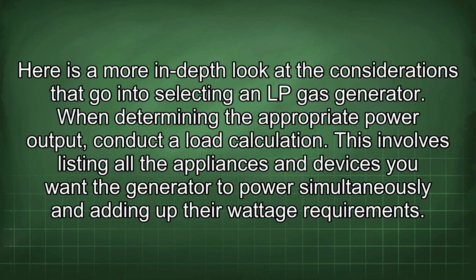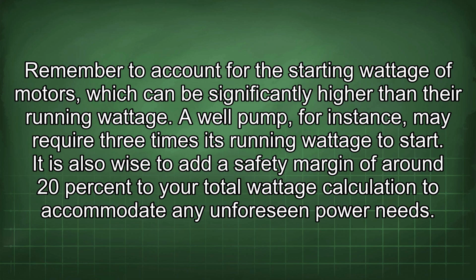Here is a more in-depth look at the considerations that go into selecting an LP gas generator. When determining the appropriate power output, conduct a load calculation. This involves listing all the appliances and devices you want the generator to power simultaneously and adding up their wattage requirements. Remember to account for the starting wattage of motors, which can be significantly higher than their running wattage.